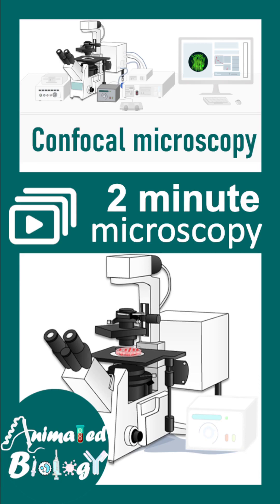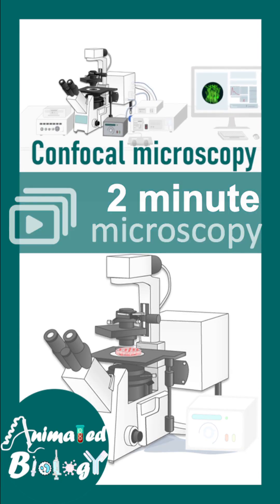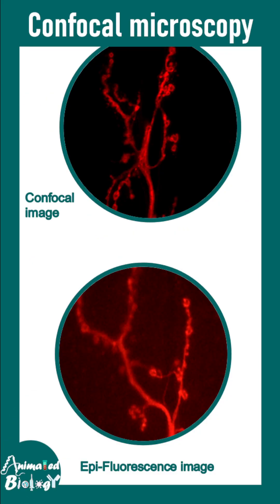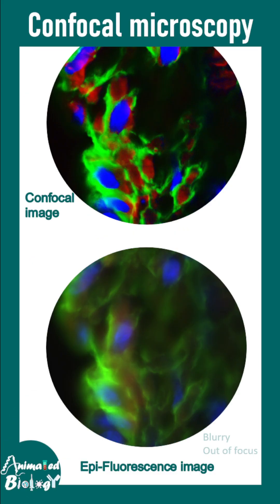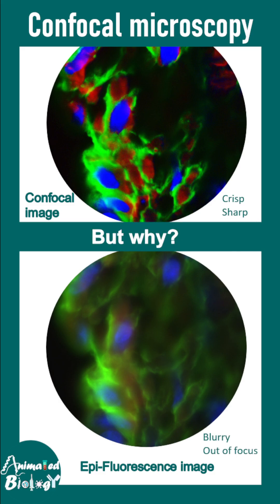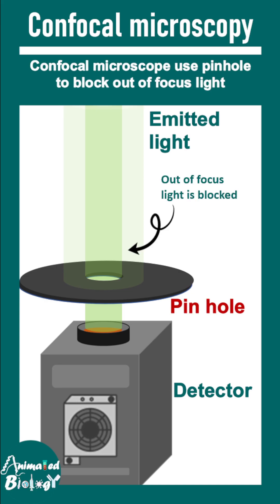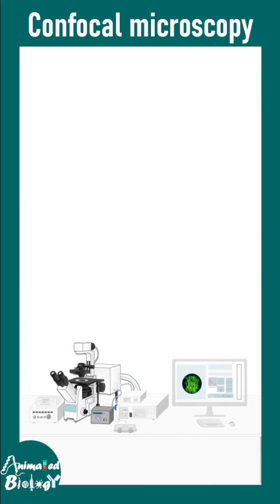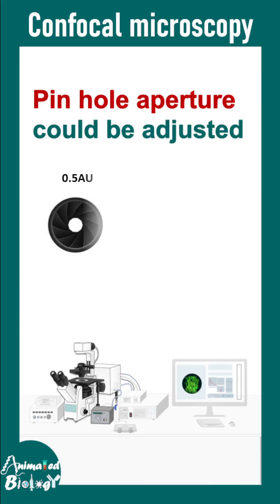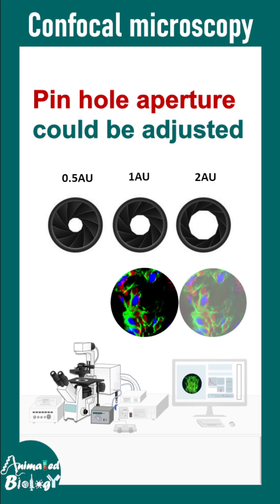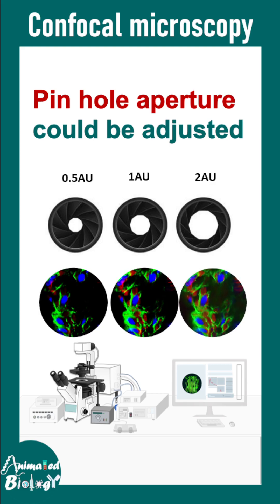Welcome to Two Minutes Microscopy. In this installment we'll talk about confocal microscopy, which works on the principle of fluorescence. Confocal images are sharper and crisper — the reason lies at the heart of the confocal: a pinhole, which blocks all out-of-focus light. The pinhole aperture can be adjusted in the confocal, and based on how we adjust it, the contrast and signal will differ.